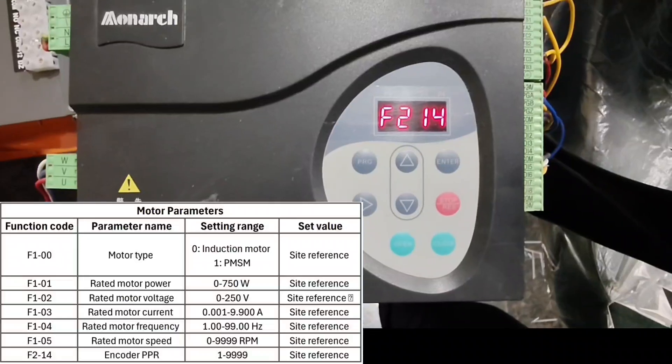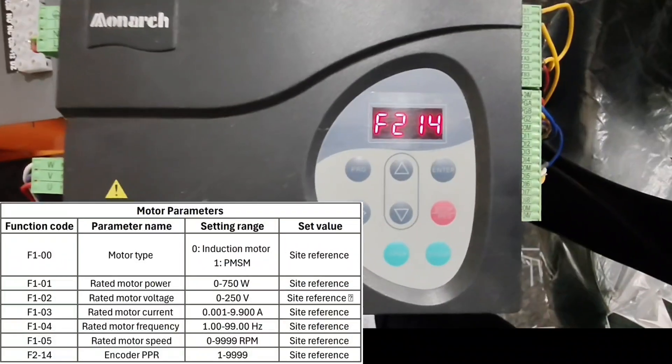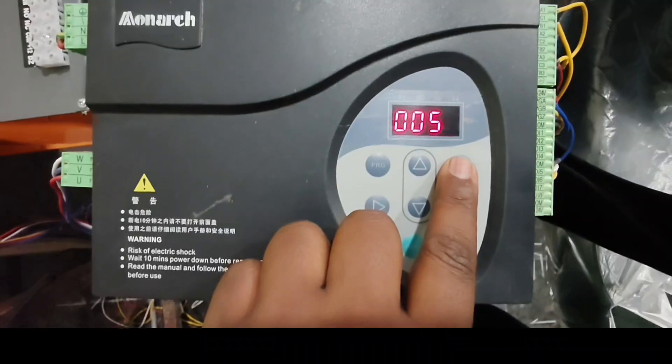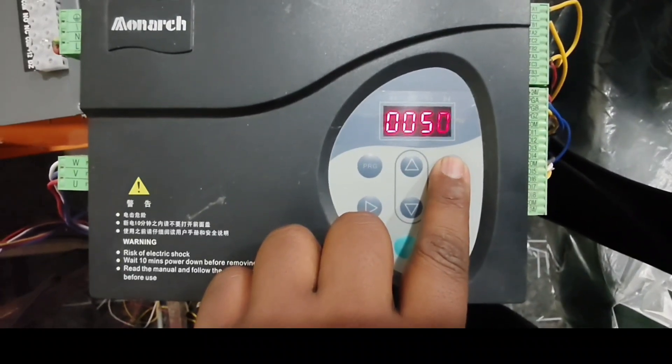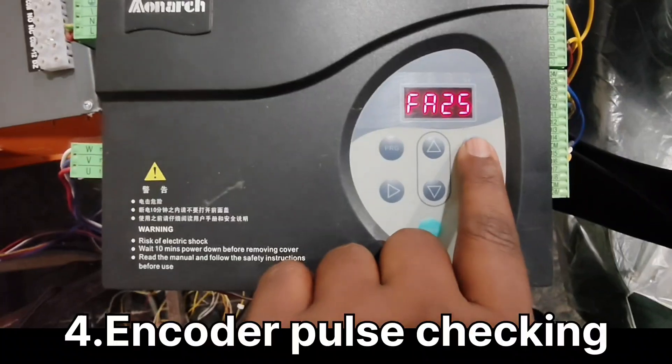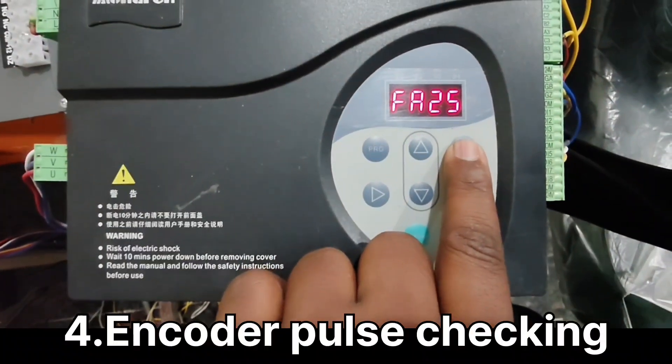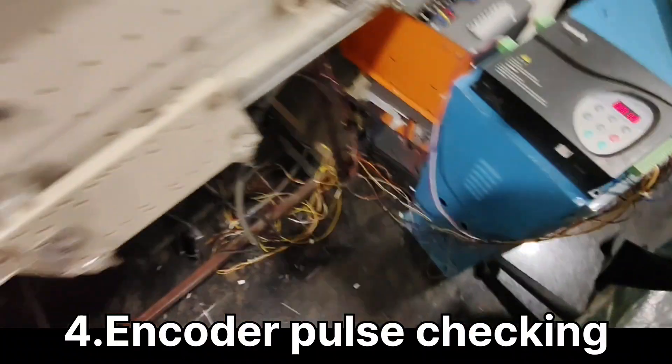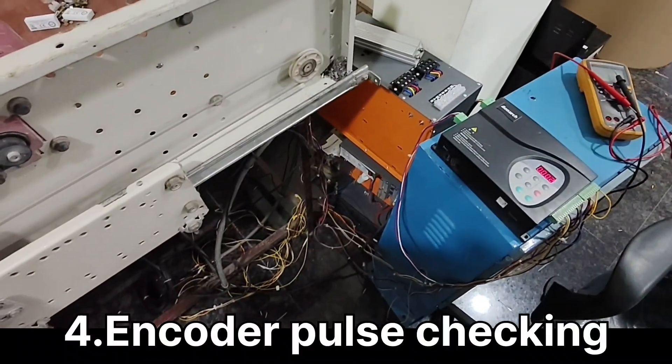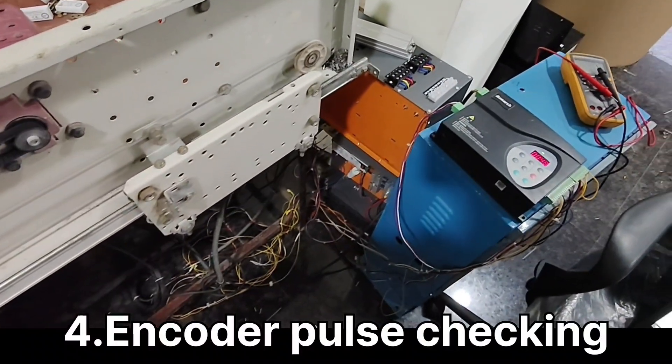After this, door motor encoder PPR value needs to be set in F214 to 50 pulse. Check encoder pulse in FA25. Move the doors and the value will change.